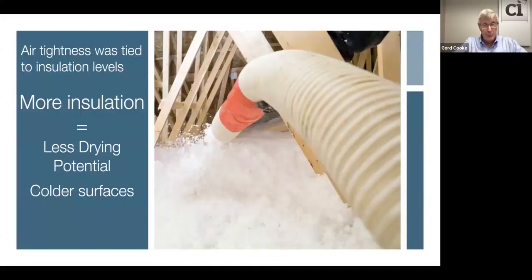I do want to say, from a code perspective, and then from a practicality standpoint, air tightness was tied to insulation levels. The key to understanding here is the more insulation you put in an attic, for example, or a wall, the less drying potential there is in that wall. Heat flow through the wall created tremendous drying potential, and it means the backside of the cavity gets colder and colder.